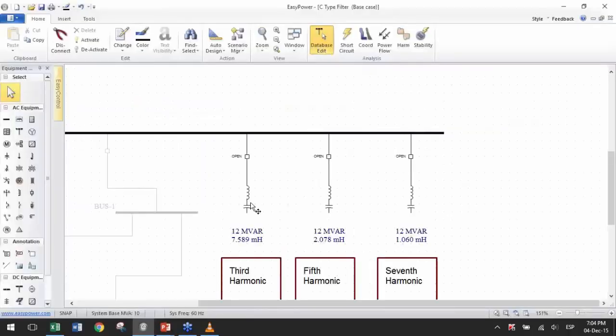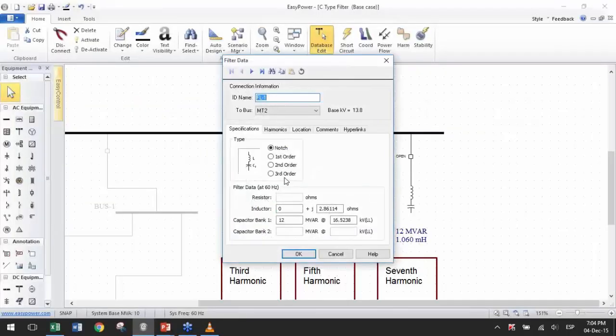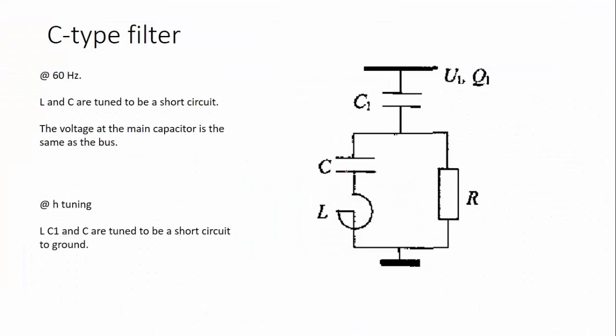You may see that it's quite close to what EasyPower offers, let's say the third-order filter, which has a capacitor and a series combination of R and C and L, well, parallel L. But the C-type filter is different because what you have in series is not C and R, but C and L. This is called the tuning branch. This is the tuning branch. This is the main power capacitor, and this is a resistance. The attenuation comes from this resistance.